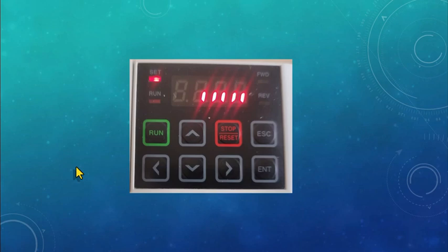In IN87, if the bit related to that digital input is low, meaning it's deactivated, then the contact of that digital input is in the normally open state. And if its bit is high, meaning it's active, then the contact is normally closed.